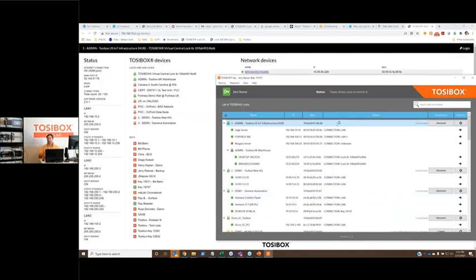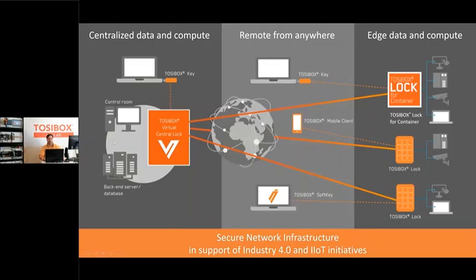With just a few checkboxes, a radio button, and a save, I've added those networks to my data center network. In 15 to 30 seconds these icons will turn green, confirming that this lock and that top lock have negotiated their own fully secure point-to-point connection to the data center. Through this we can communicate BACnet IP from our building controllers, and Profinet, OPC UA, Modbus, and more on our industrial controllers, all up to a centralized location running a historian, a SCADA system, or a web supervisor, across our entire global network.